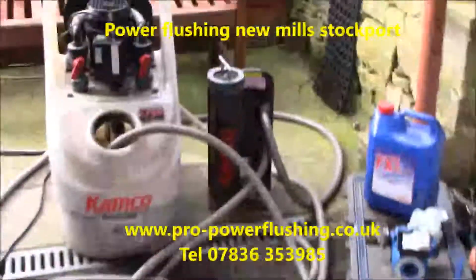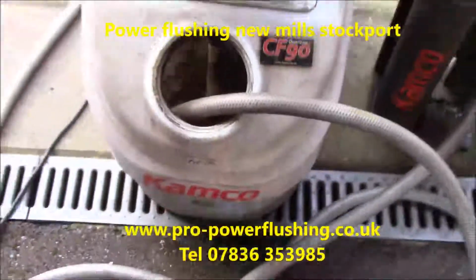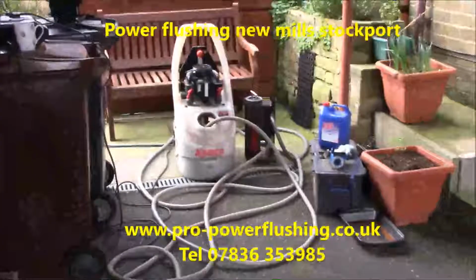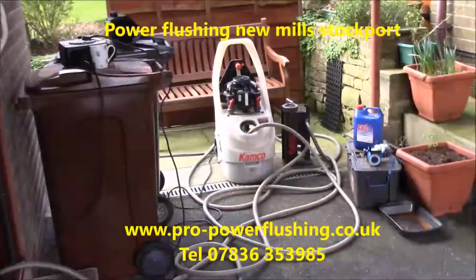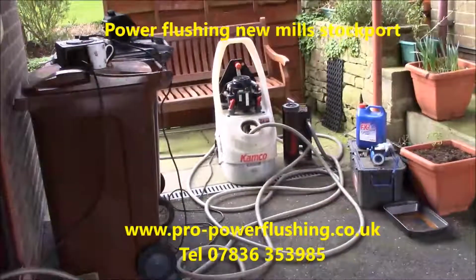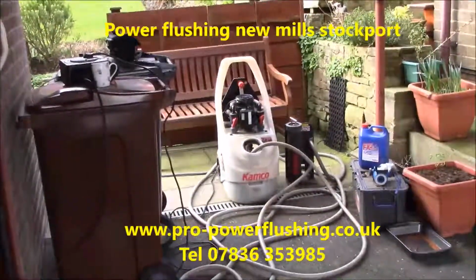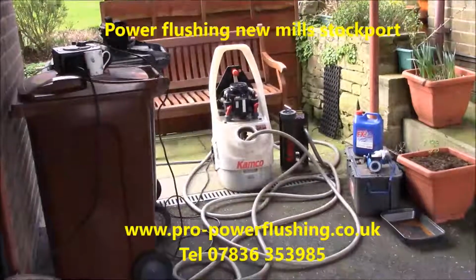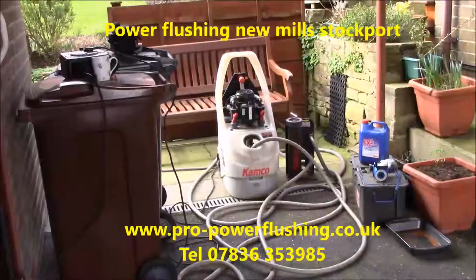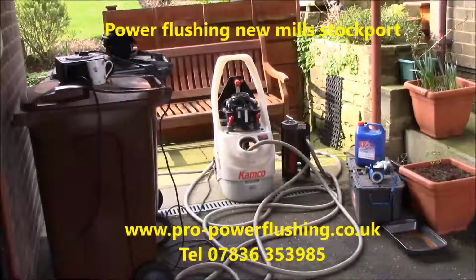We'll just show you again. Like engine oil. Obviously we showed you that pipe that was blocked up before, very badly blocked up. And we're hooked into the system now. We've got a good flow around the system. In fact, apparently British Gas did come back. They cleared a pipe up near the hot water cylinder, but the pipes they didn't clear were the pipes coming down from the feed and vent tank. They were completely blocked. So we hooked in through the pump, which is underneath the floorboards.